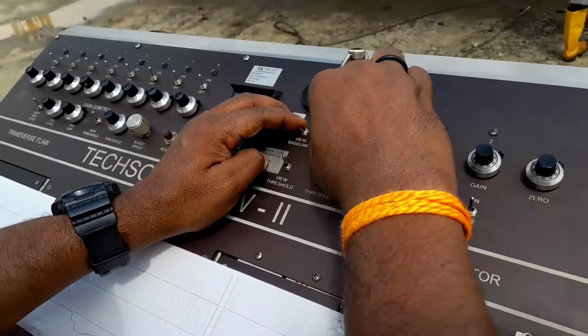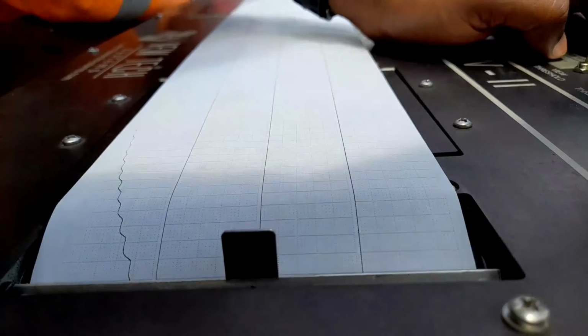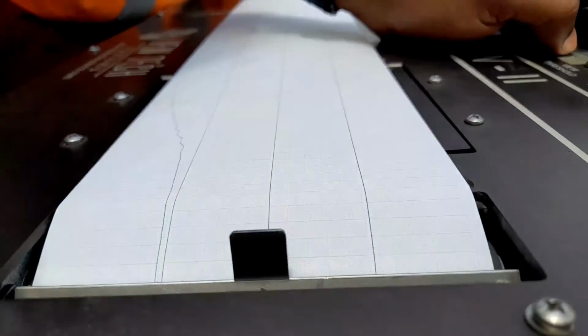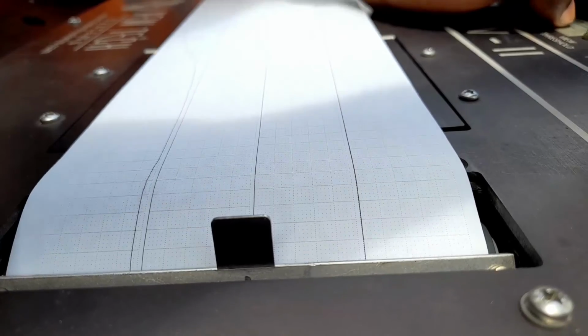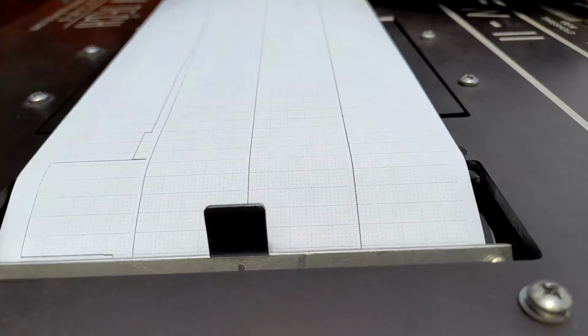Next is wall monitoring setup. Also have 3 methods. Before you start your base, check your baseline. Hold the baseline toggle switch and adjust the value 1 mm, in between 1 to 5 mm. 1 mm is okay. You can get maximum accuracy. 1 mm or 2 mm from top. Always remember from top. All others we set up from bottom, and in this wall monitoring section the baseline is set up on the 1 or 2 mm from the top.